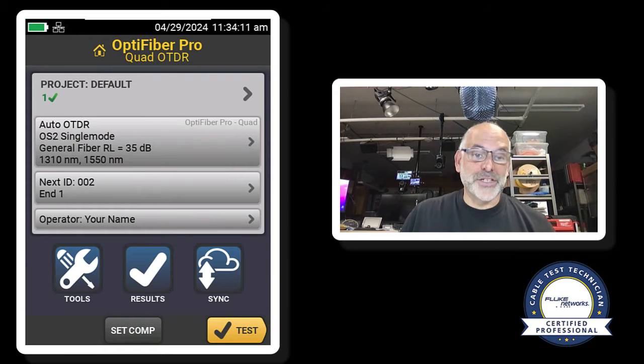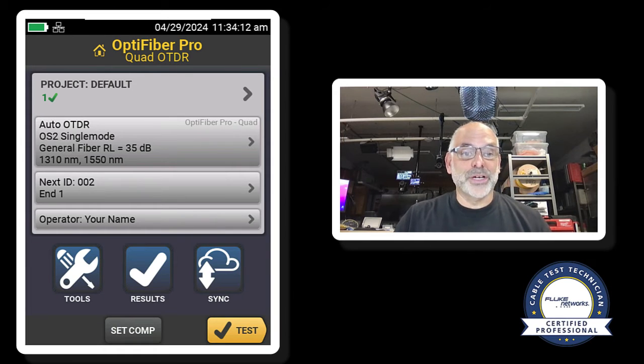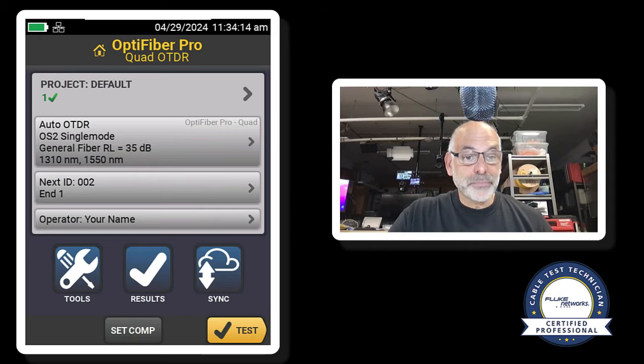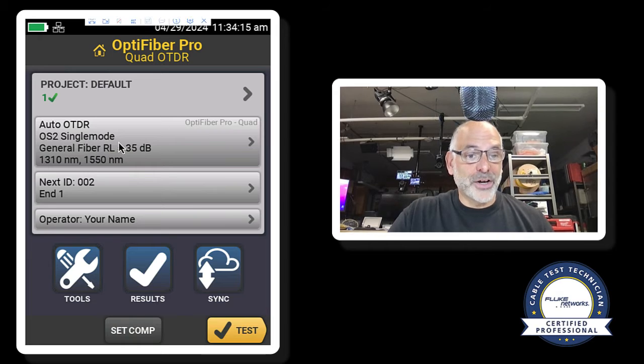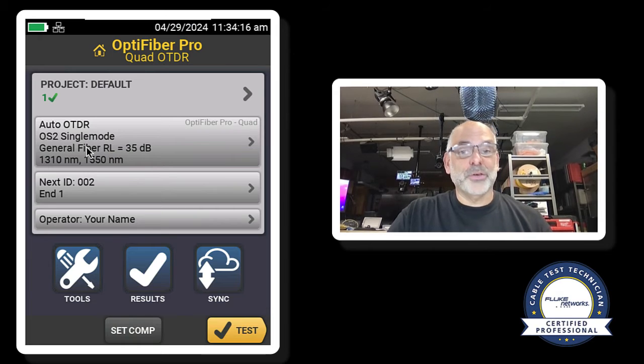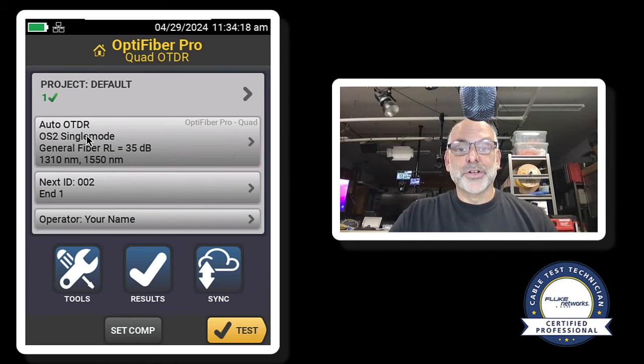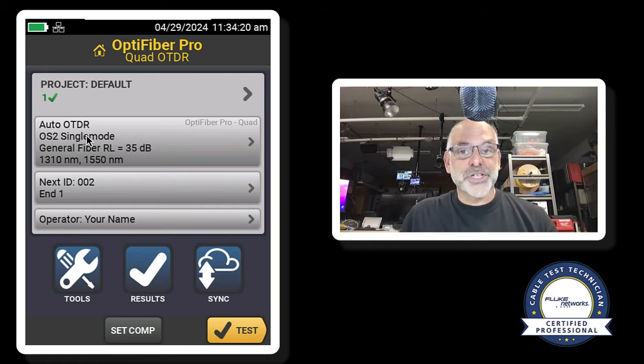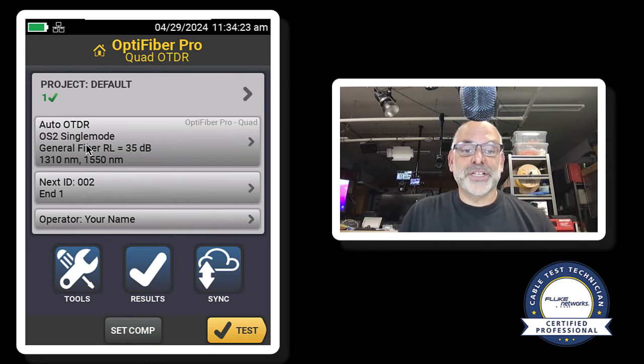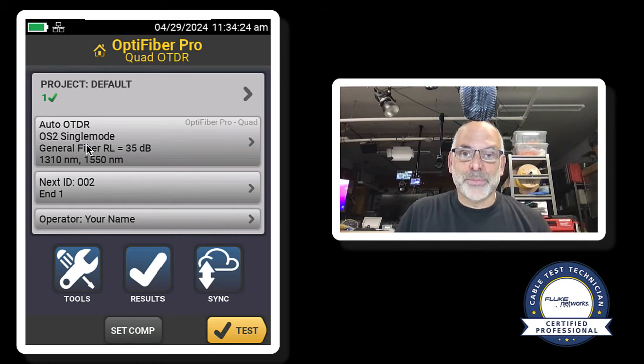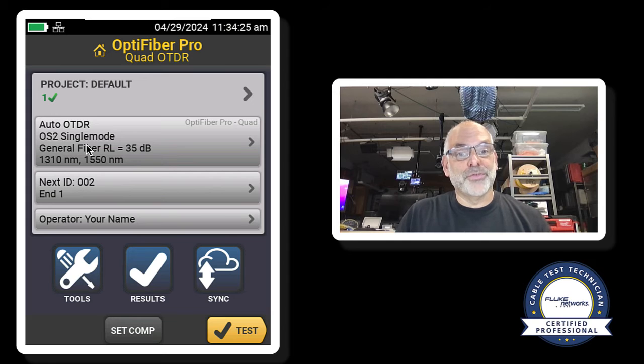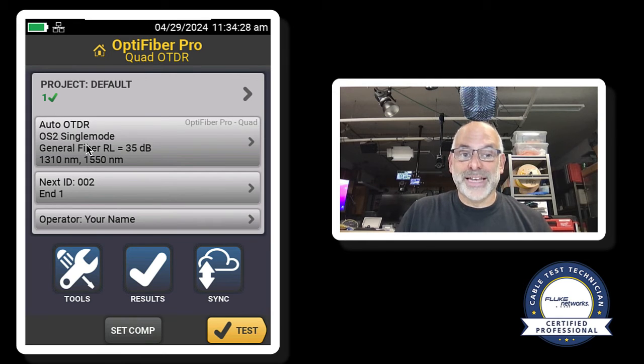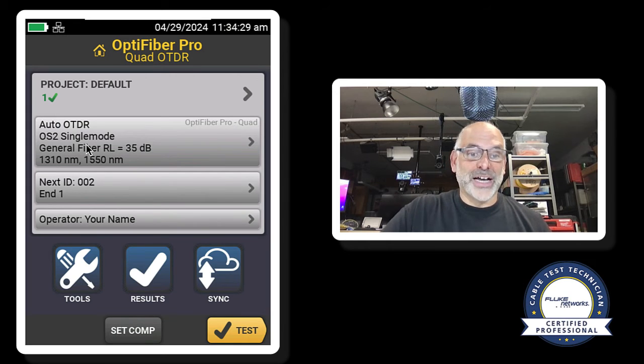So in this case, when we take a look at our test setup, we've got our auto OTDR. We are doing OS2 single-mode fiber. We've got our test limit set to general fiber, and we're looking for a reflectance of less than negative 35.